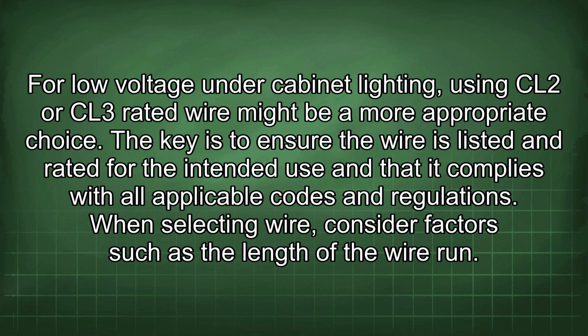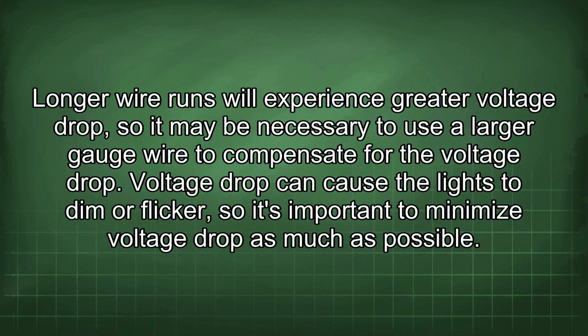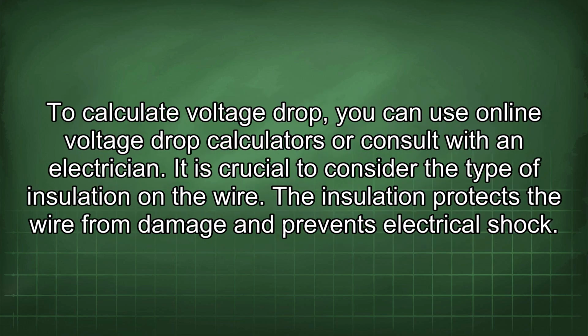When selecting wire, consider factors such as the length of the wire run. Longer wire runs will experience greater voltage drop, so it may be necessary to use a larger gauge wire to compensate for the voltage drop. Voltage drop can cause the lights to dim or flicker, so it's important to minimize voltage drop as much as possible. To calculate voltage drop, you can use online voltage drop calculators or consult with an electrician. It is crucial to consider the type of insulation on the wire.